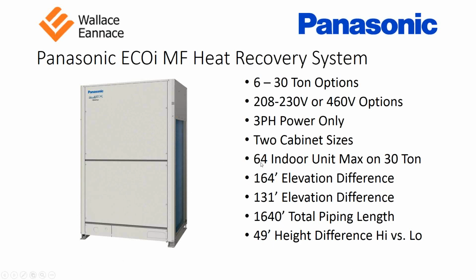The max amount of indoor units on the 30-ton is the same at 64 indoor units max. The elevation differences are the same, 164 feet when the condenser's on the roof that you could pipe down. When the condenser is on the floor, you can pipe up to a highest elevation of 131 feet. The total amount of piping length for this system is less. It's 1,640 feet total. And the height difference between the highest indoor unit versus the lowest indoor unit is the same at 49 feet.